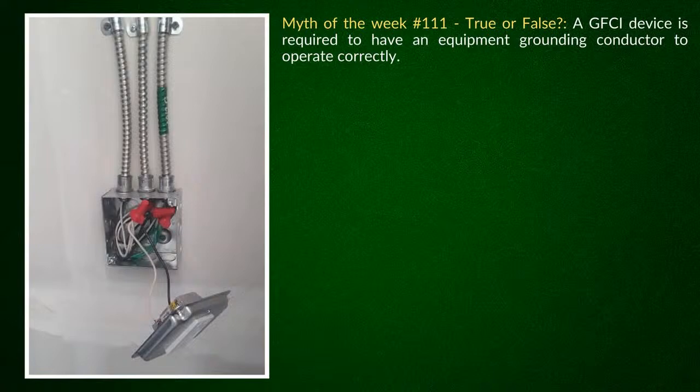But this brings up an interesting point, because if you look at the UL standards, me and James kind of harped on this a lot. When you're going to test these, you're supposed to test them monthly. Like, I know you test yours monthly over there at the Stallcup Ranch. But what you're supposed to do is actually use the test button on the device.